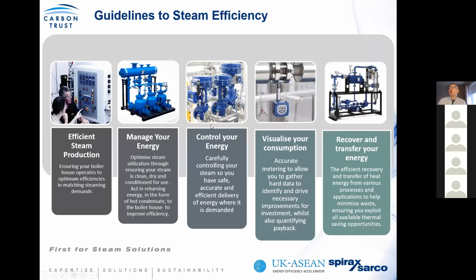We mentioned controls. Again, remember the classification of valve is the process on off, whether you're in optimum control or not. Because a lot of times we have found that control is lacking, and the very nature in which a steam valve operates, for example, if it rapidly goes from 0 to 100%, has a big impact on the boiler house. Again, Dave mentioned the metering.